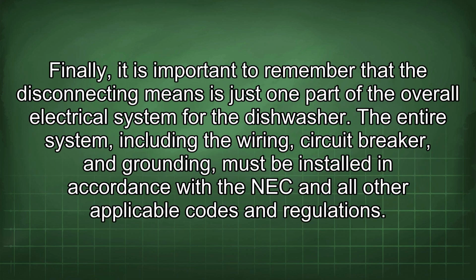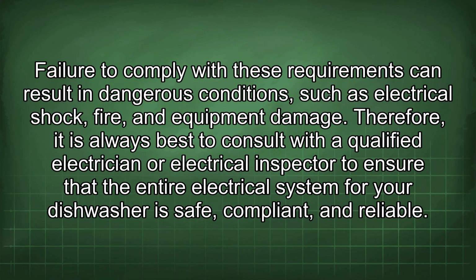Finally, it is important to remember that the disconnecting means is just one part of the overall electrical system for the dishwasher. The entire system, including the wiring, circuit breaker, and grounding, must be installed in accordance with the NEC and all other applicable codes and regulations. Failure to comply with these requirements can result in dangerous conditions such as electrical shock, fire, and equipment damage. Therefore, it is always best to consult with a qualified electrician or electrical inspector to ensure that the entire electrical system for your dishwasher is safe, compliant, and reliable.